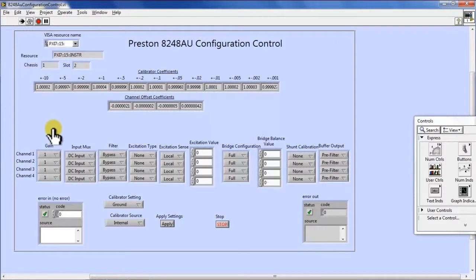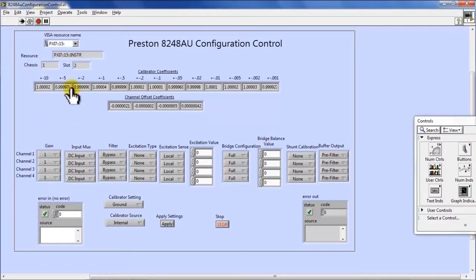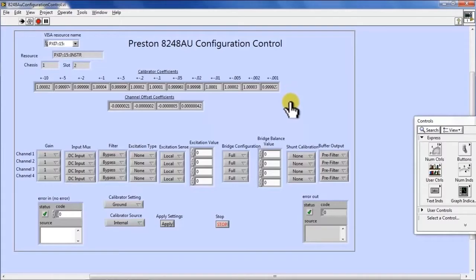As you can see the same columns and rows are available and with the same functionality including all the gain coefficients for both the hybrid calibrator and the channel offset coefficients.